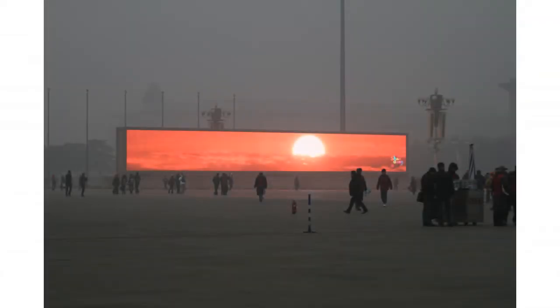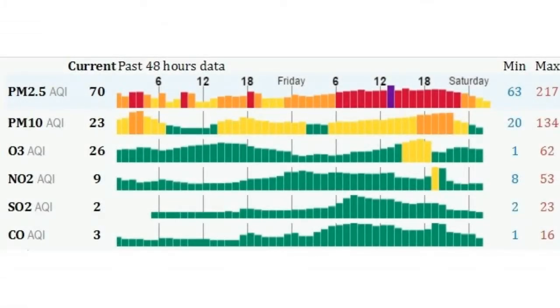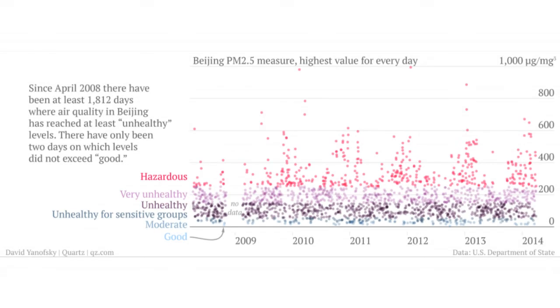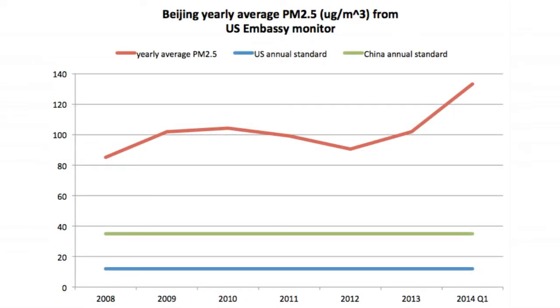Taking into account the well-known conditions of the outside air in China, even more in Beijing, we had made great efforts to supply the occupants with well-filtered, fresh air. Outdoor air monitoring equipment was mounted near the fresh air inlets in order to continuously follow the outside air quality, as the table shows. The diagram shows the concentration of PM 2.5 pollutants for every day the highest value, from 2009 to 2014. Since April 2008, there have been at least 1,812 days where air quality in Beijing had reached at least unhealthy levels. There have been only 2 days on which levels did not exceed good.